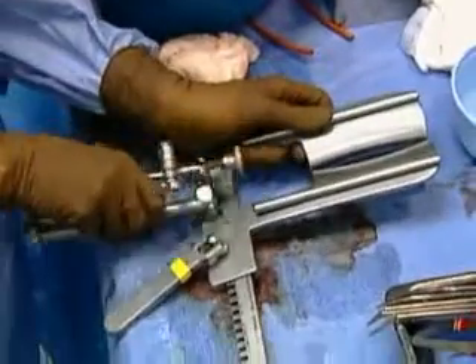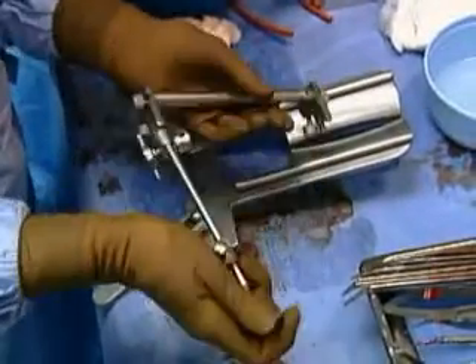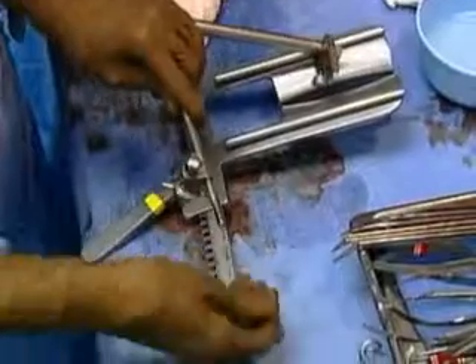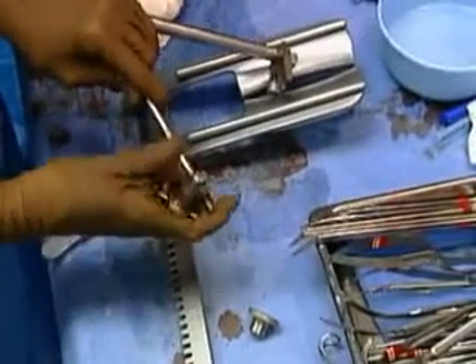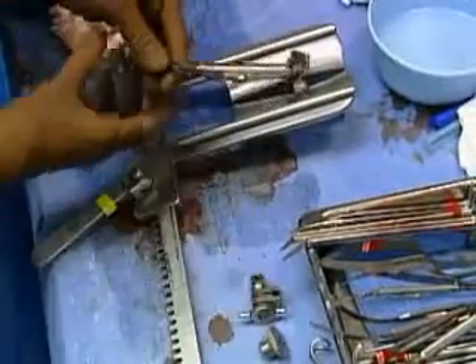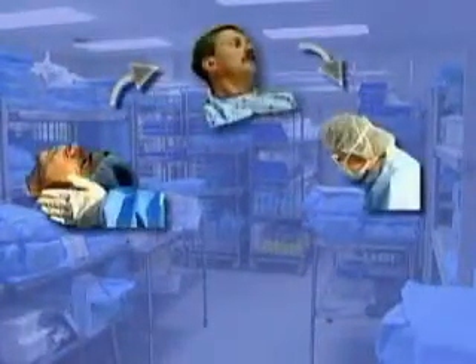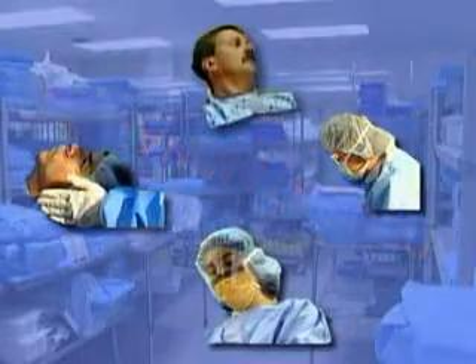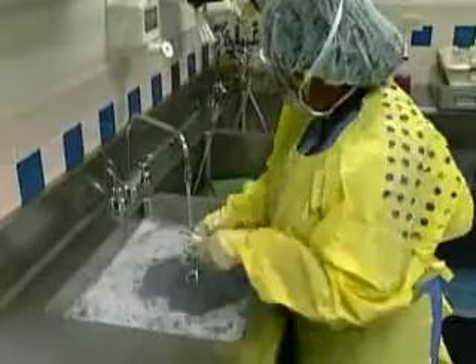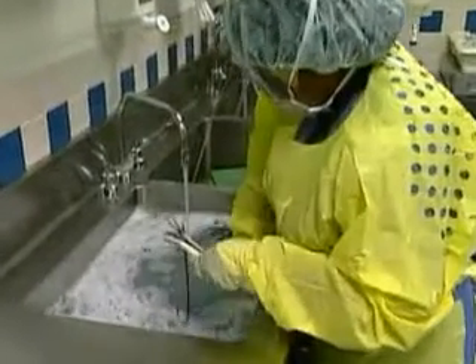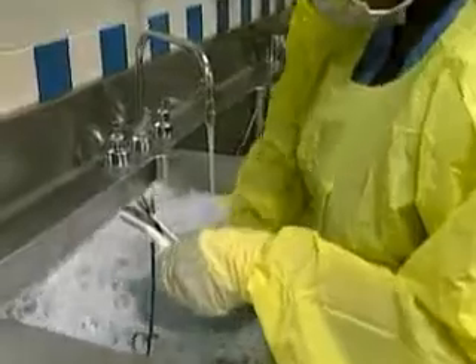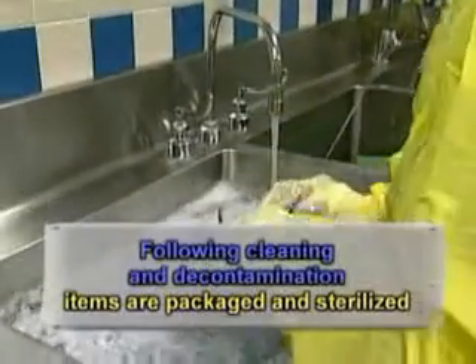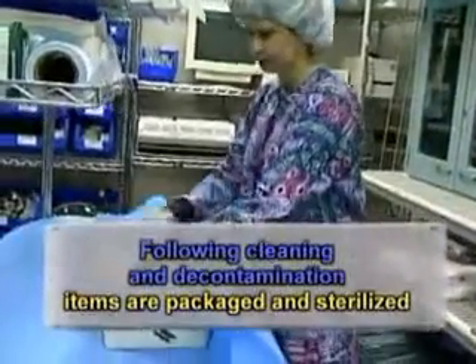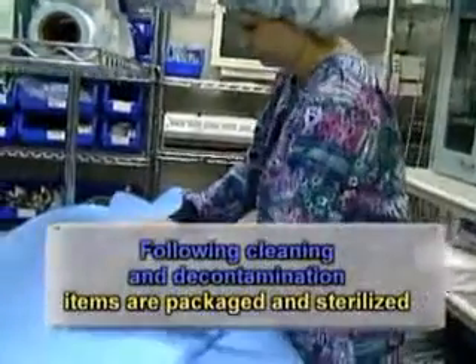Regardless of the method chosen to clean the instruments, all items with detachable parts that can be separated need to be disassembled for cleaning, packaging, and sterilization. Decontamination is the critical step in breaking the chain of cross-infection between patient and patient and between patient and worker. Sterilization cannot be achieved if items are not thoroughly cleaned of the protein soil. After the cleaning and decontamination process, items should be prepared and packaged so sterility can be achieved and maintained to the point of use.